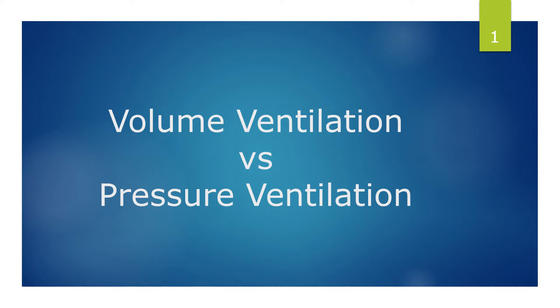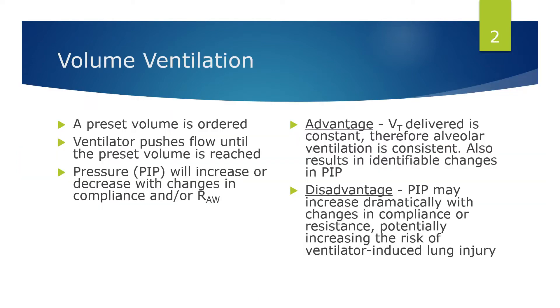In this lesson we will be differentiating between volume ventilation and pressure ventilation. With volume ventilation there is going to be a preset tidal volume ordered by the physician. When we put that preset volume into the ventilator, it will push the same tidal volume in each and every breath — the tidal volume will not change. The ventilator pushes flow until the preset volume is reached.